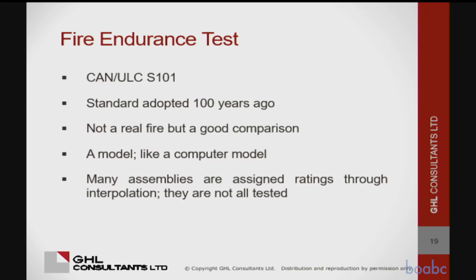So the fire test is a model. I mean, it's a real fire. They build a wall and they put it in a furnace and they light it on fire, but it's not a real fire in terms of how a fire would behave inside a room or a building. So it's like a model, and it's been around for 100 years. And if you look up fire testing in Japan and fire testing in Australia and fire testing in the UK, they're all exactly the same. There's one fire test in the world. We call it S101, they all call it something else, but basically there's one test.